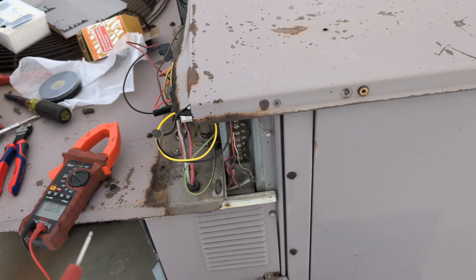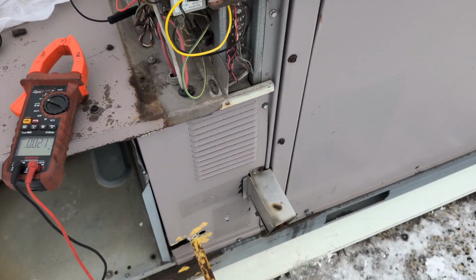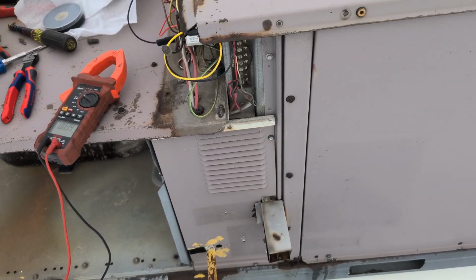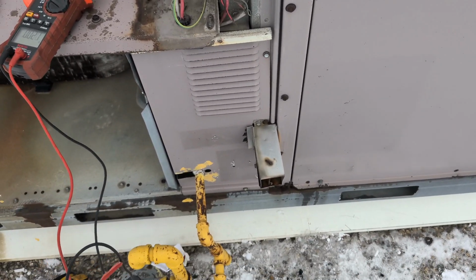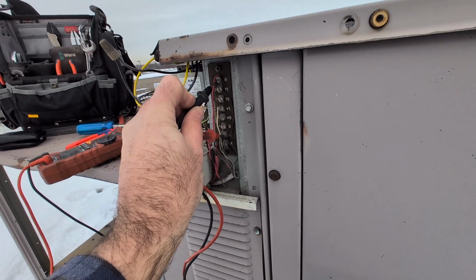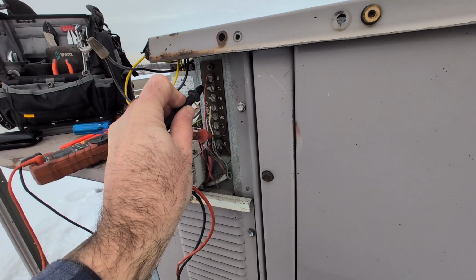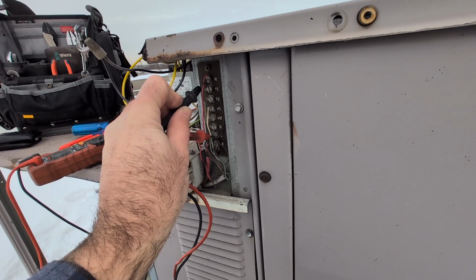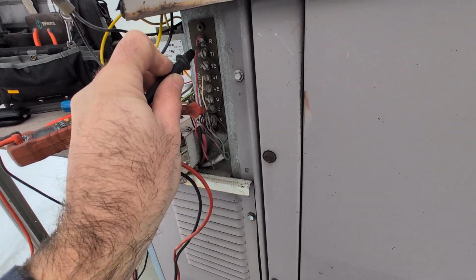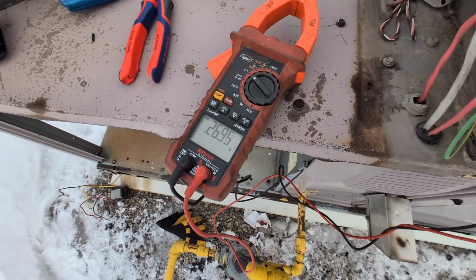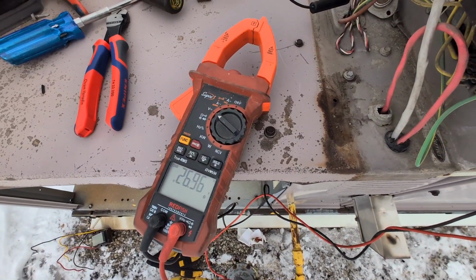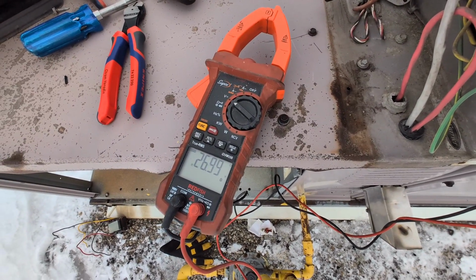All right, so replacing the transformer, throwing in the fuse. I turned the machine back on, the fuse didn't pop, and we are running. Let me show you here. Originally, we had no control voltage because our transformer was defective. So now I'm checking between R and common. We go to our meter, the Supco meter here. We got 26 volts, so we're all good to go.